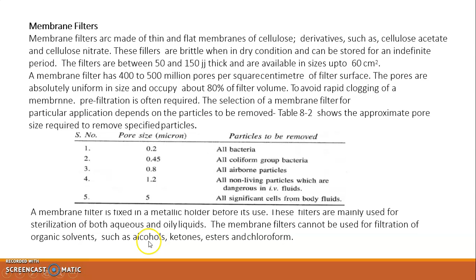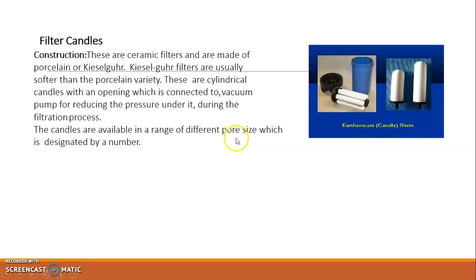Then filter candles. Construction: these are ceramic filters made up of porcelain or Kieselguhr. Kieselguhr filters are generally softer than the porcelain variety. These are cylindrical candles with an opening connected to a vacuum pump for reducing the pressure under it, which speeds up the filtration process. The candles are available in a range of pore sizes, which are designated by numbers.